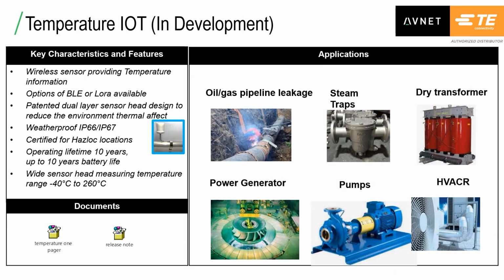TE's wireless temperature sensors will also be available in early 2025 and provide reliable temperature sensing in a rugged and reliable package. Like the rest of the wireless sensing portfolio, there are options for both BLE and LoRa communication, as well as intrinsically safe certification, long battery life, and much more. These sensors are built using a patented dual-layer sensor head design that allows for accurate temperature sensing at high temperatures up to 260 degrees C, while isolating the sensor head and electronics from the high temperatures. Applications include corrosion under insulation for oil and gas pipeline systems, steam traps, transformers, power generators, pumps, and HVAC applications.